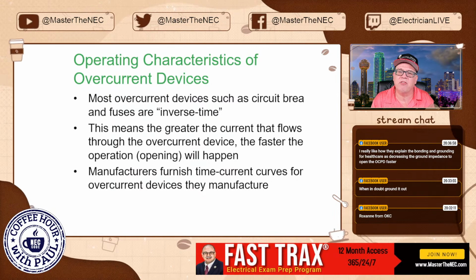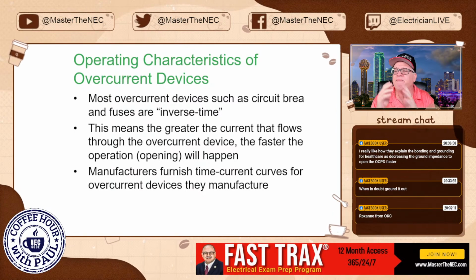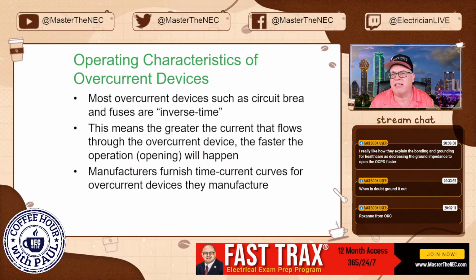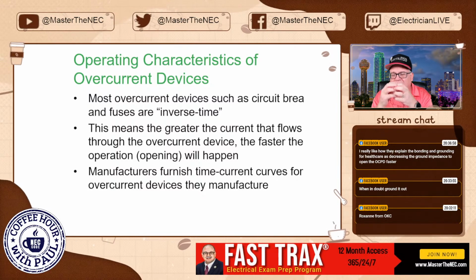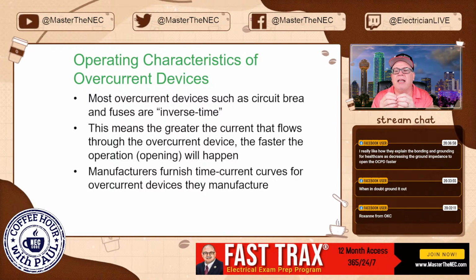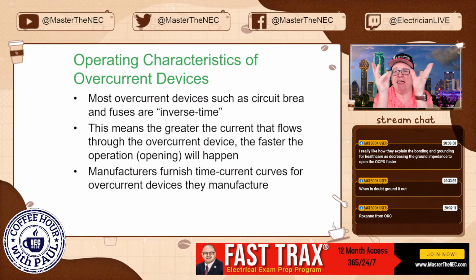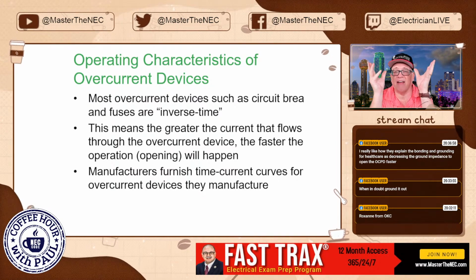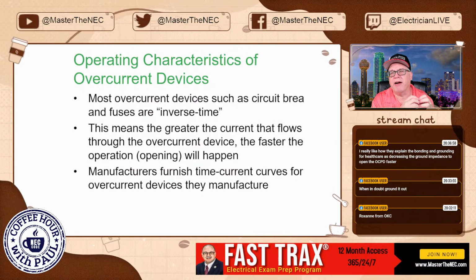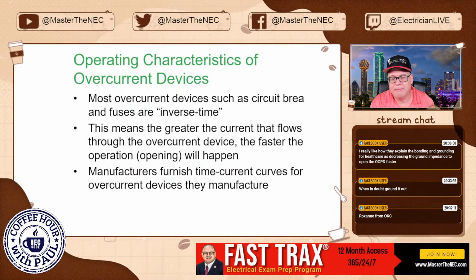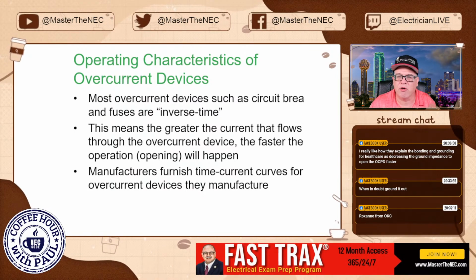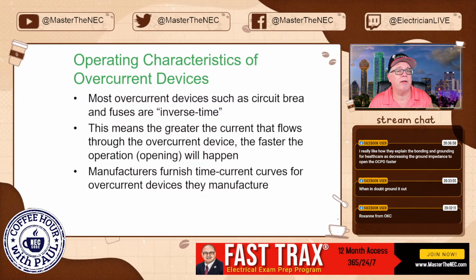But what happens is, if you construct this path, if you do it right, if you connect everything right, that means at that fault, it's going to allow that current to skyrocket. And the more it skyrockets, the quicker that breaker is going to react. And that's what we mean by inverse time or inversely proportional.